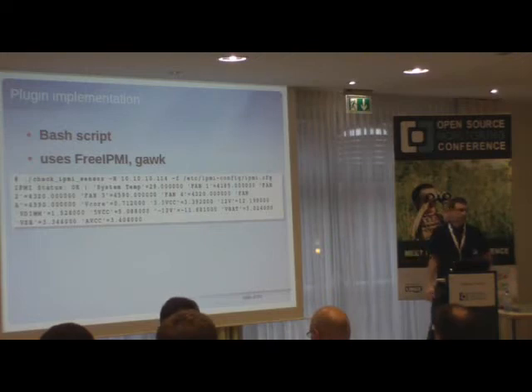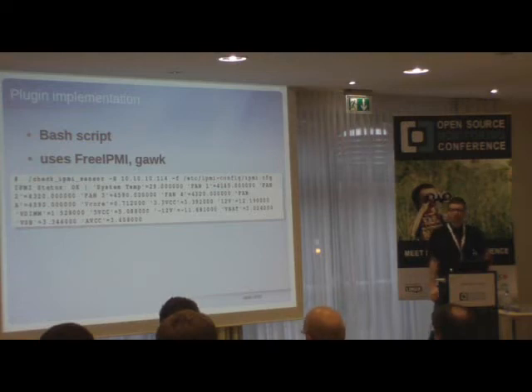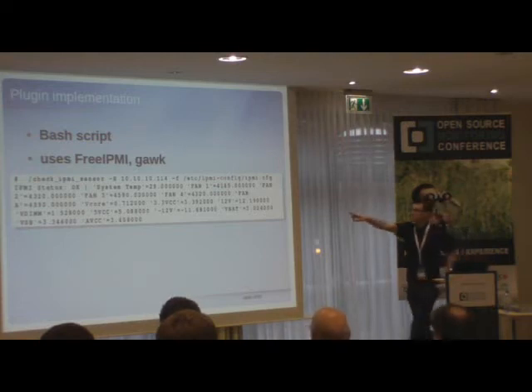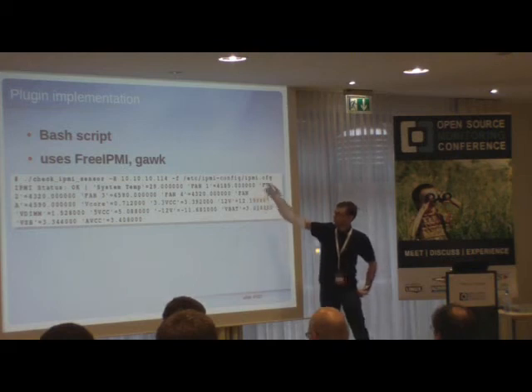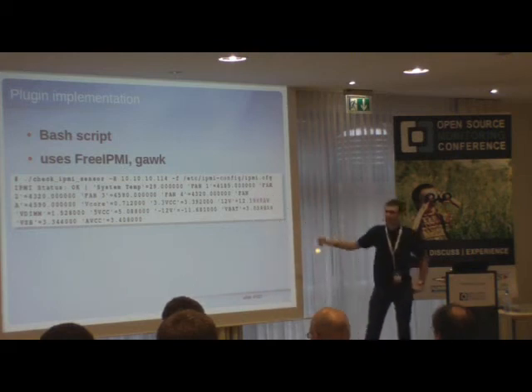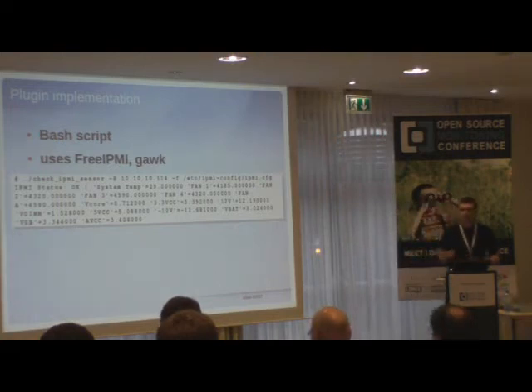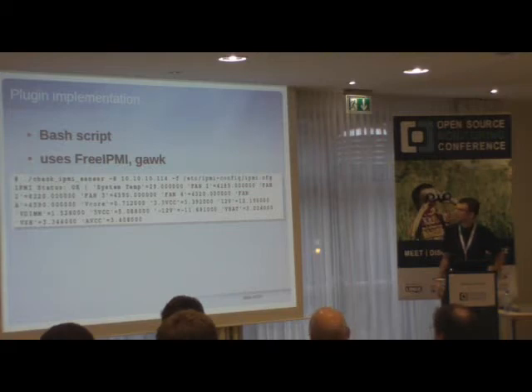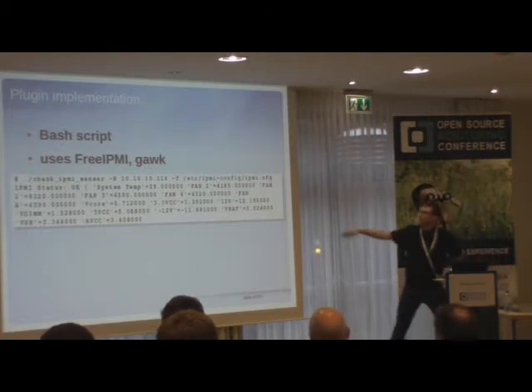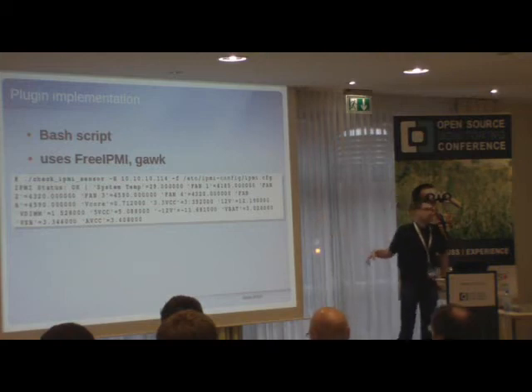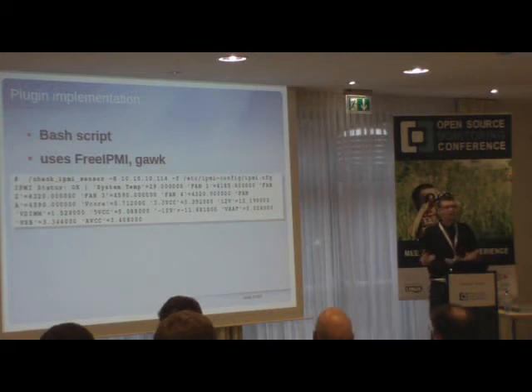The output follows the Nagios plugin development guidelines: status information, then a pipe symbol followed by performance data, and a return code indicating OK, warning, or critical. In this case everything is fine — all sensors are okay — and we get values for all threshold-based sensors as analog readings, which can be used with PNP for Nagios, Ingraph, or similar graphing tools.